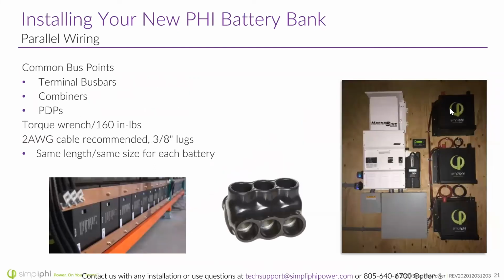Do not wire the batteries in series, so only wiring them in parallel to a common bus point. So I'm talking individual cables from each battery to a combiner or even a terminal block like this. You can also slap some very thick, beefy bus bars on the terminals of the batteries. And what you're going to do then is drill holes in those bus bars so that they fit the batteries exactly. Now, we do sell bus bars made for 3 batteries, but we do not sell bus bars made for more than that. So you'd have to get something custom.